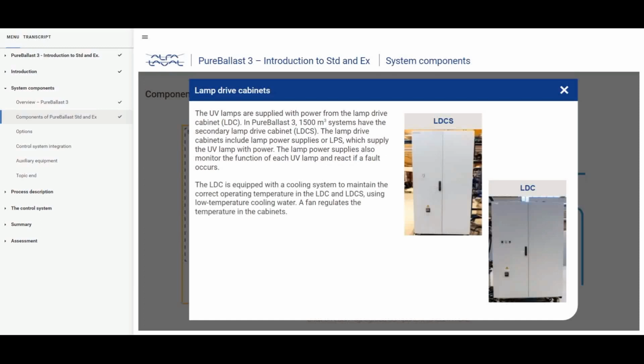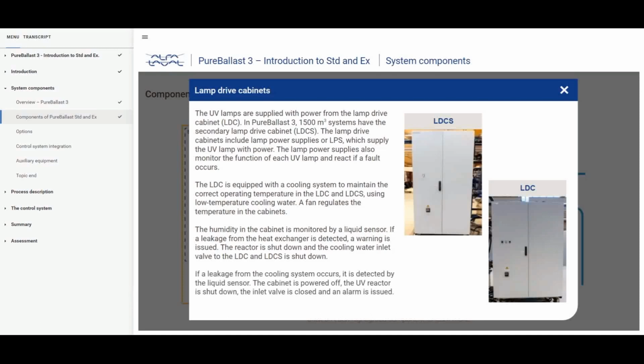The lamp drive cabinet is equipped with a cooling system to maintain the correct operating temperature in the lamp drive cabinet and secondary lamp drive cabinet, using low temperature cooling water. A fan regulates the temperature in the cabinets. The humidity in the cabinet is monitored by a liquid sensor. If a leakage from the heat exchanger is detected, a warning is issued. The reactor is shut down, and the cooling water inlet valve to the lamp drive cabinet and secondary lamp drive cabinet is shut down. If a leakage from the cooling system occurs, it is detected by the liquid sensor. The cabinet is powered off, the UV reactor is shut down, the inlet valve is closed, and an alarm is issued.